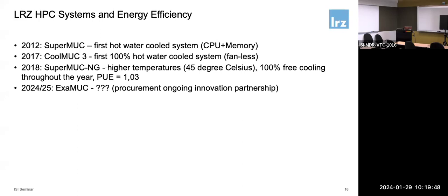If you look at today's systems, there are many hot water cooled systems, but most of them only go up to 20 or 25 degrees Celsius. We are now at 45 degrees Celsius, which means we can run throughout the year without any additional cooling. That gives us a power usage effectiveness of 1.03 — a number we'll see again in a second.